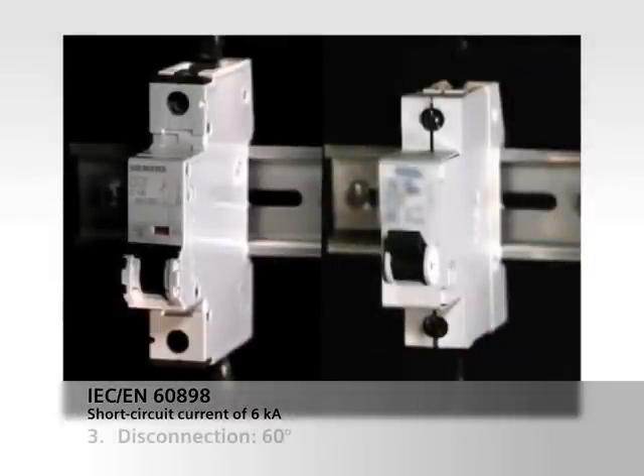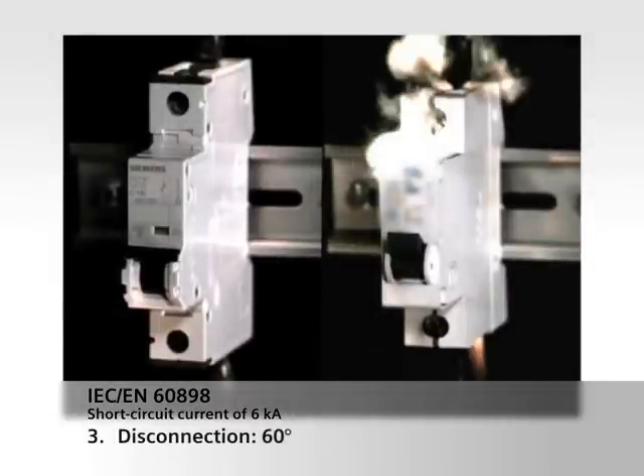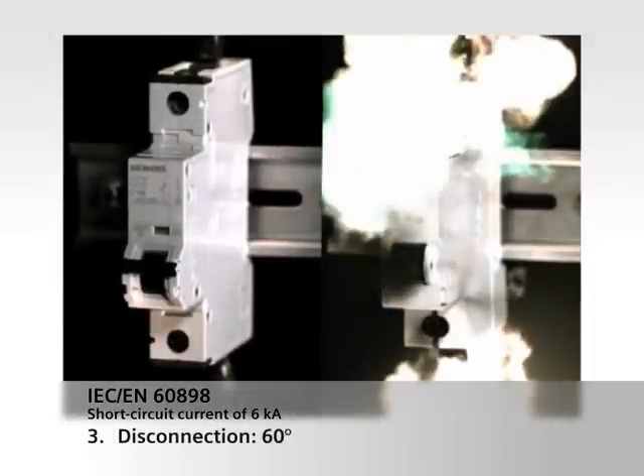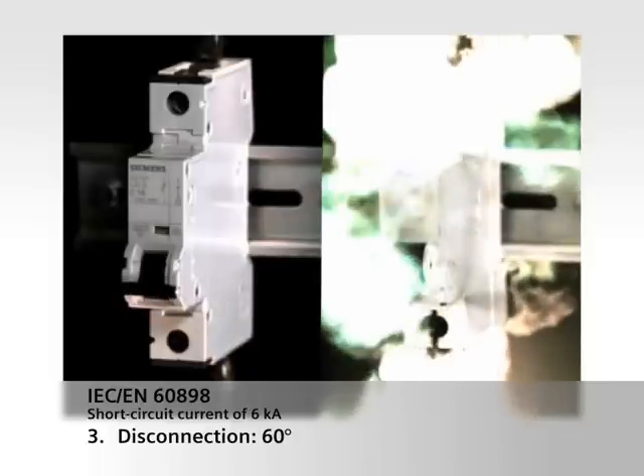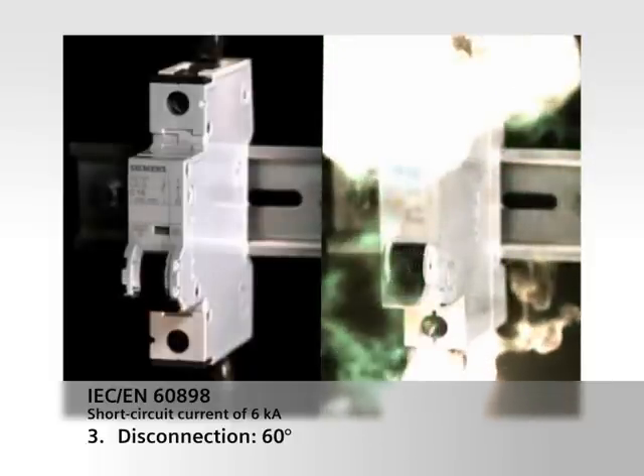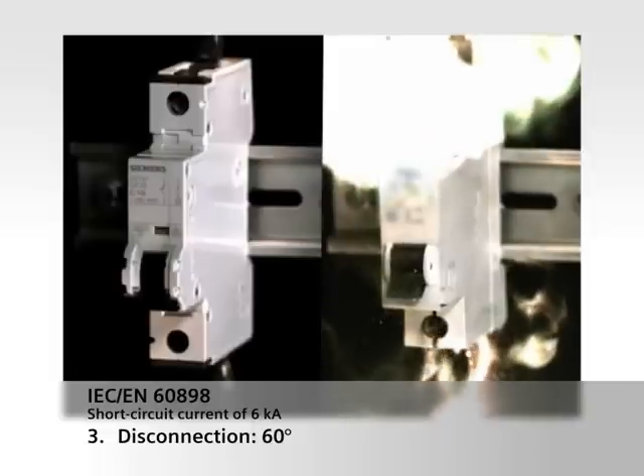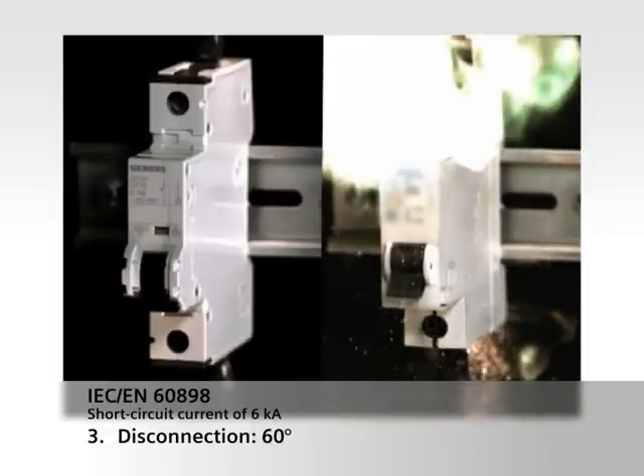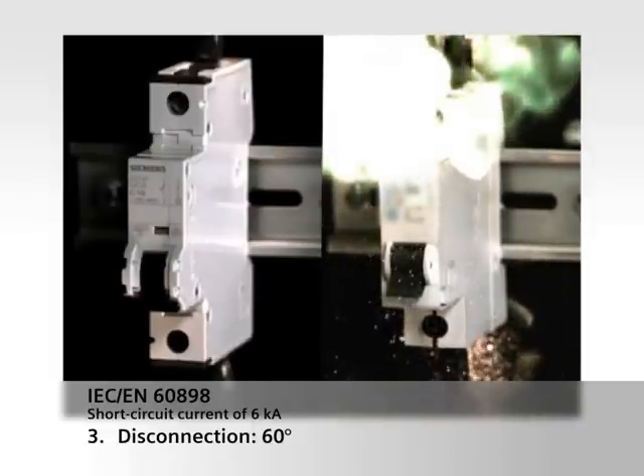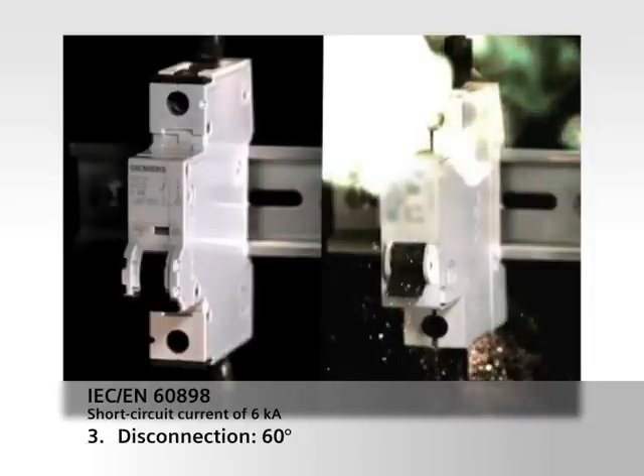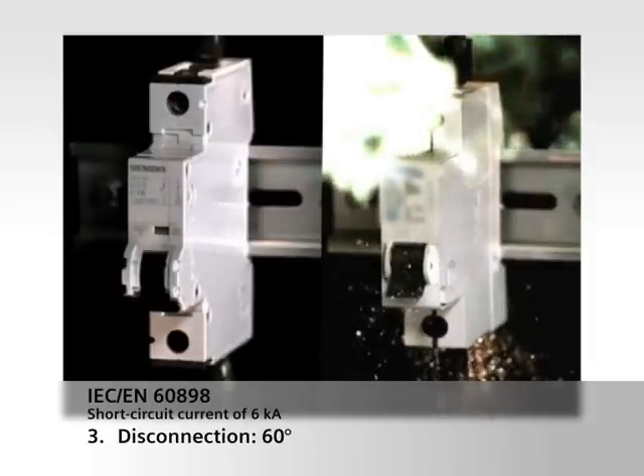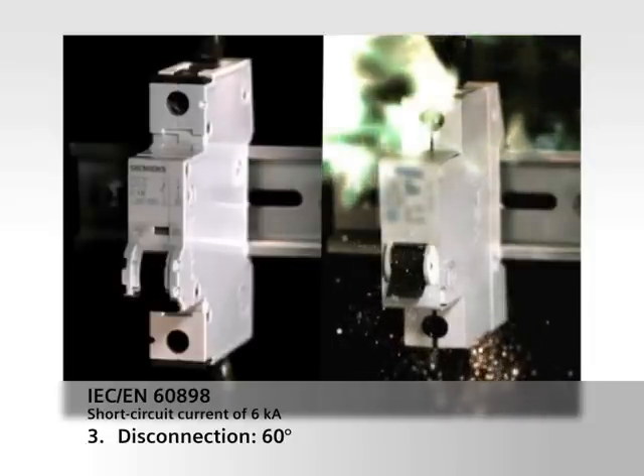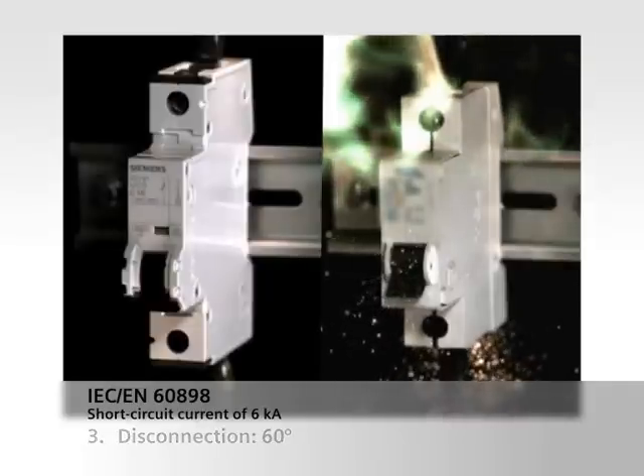The third and final test is also performed at an actuating angle of 60 degrees. As with the first two tests, the miniature circuit breaker from Siemens isolates the current quickly and safely. However, the other device has now failed completely and is no longer working at all. The flames shooting out are damaging adjacent devices, and there's a considerable risk of a fire breaking out. This also places personnel at risk.